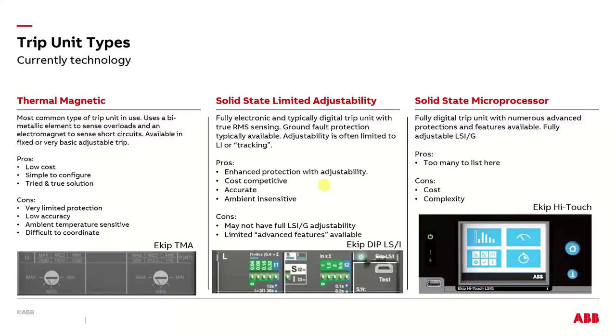So you can get a really simple adjustment, maybe what they call tracking, where you have one dial and it adjusts both the instantaneous and the long time delay all with one dial. Or you could get into a full LSI breaker, which is the breaker that has a long time, short time, and instantaneous adjustability. That was one of the other questions. So LSI stands for long time, short time, and then instantaneous, separate adjustments.